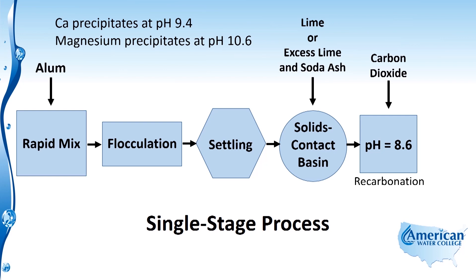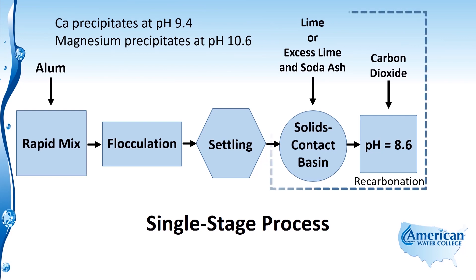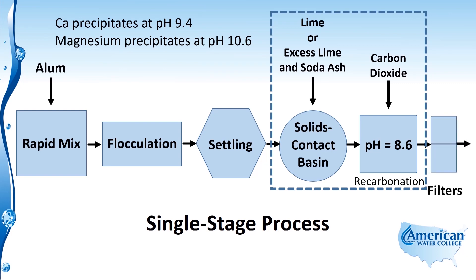Following the softening portion, we must bring the pH back down because high pH water causes problems with the disinfection process and will cause scaling in the distribution system. So we send it through a recarbonation process where carbon dioxide is added, bringing the pH down to around 8.6. From there, the recarbonated water flows to filters and then to disinfection and into the distribution system — completing the single stage softening process.